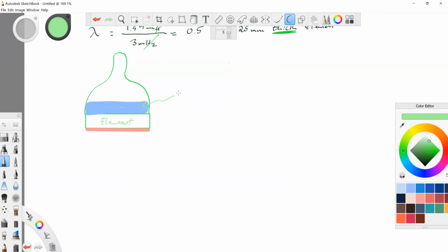I mean, okay. Epoxy, almost like a dense rubbery material. The damping material, that was the other word I was looking for. Epoxy, damping material, or backing material. I'm going to read, let's see, backing bonded. Oh, yeah, it does say right here.